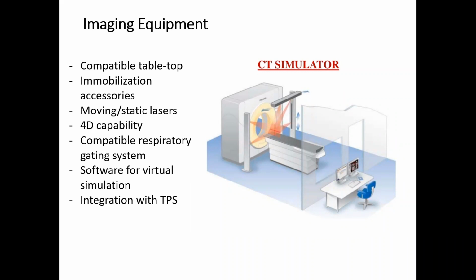If you have a 4D capability in your CT simulator, please ensure that this 4D capability and the respiratory gating are compatible with your treatment planning system and with your machine. Some of the vendors are offering 4D capability on their CT simulator which just lies on the console of the simulator. And while transferring your data bins, 4D bins, to the treatment planning system, we need to do a lot of manual work. And that's a huge risk of error.